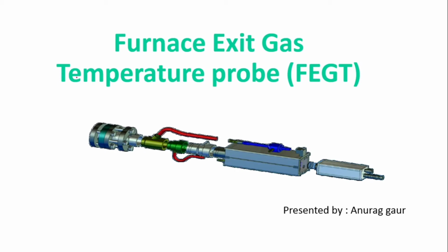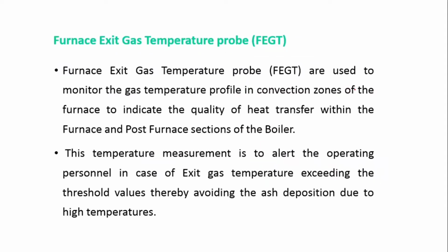Hello friend, in today's video we will discuss the furnace exit gas temperature probe, also called FEGT. Furnace exit gas temperature probes are used to monitor the gas temperature profiles in the convective zones of the furnace, to indicate the quality of heat transfer within the furnace and post-furnace sections of the boiler.